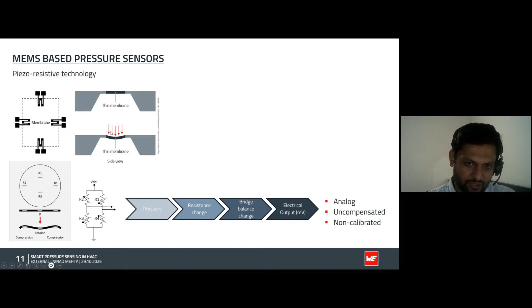A change of pressure leads to a change of resistance, and a change of resistance leads to a voltage drop across the Wheatstone bridge, which is directly proportional. So we get an analog output that is not compensated or calibrated—we don't yet know how much stress or pressure leads to how much millivolt output—but in the end we have a functional pressure sensor.